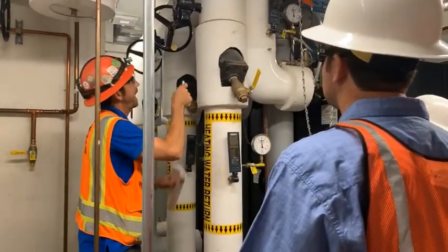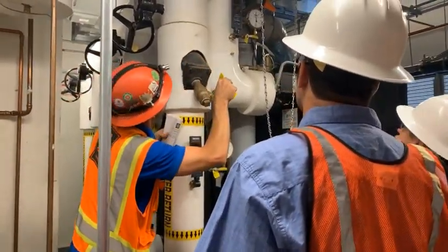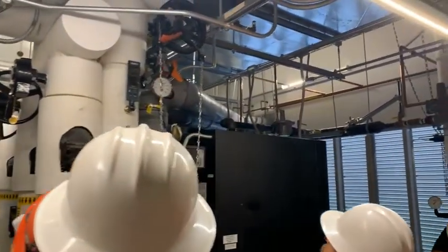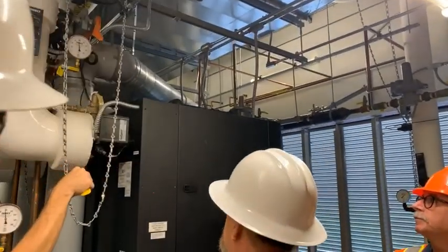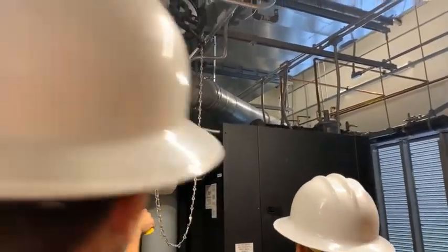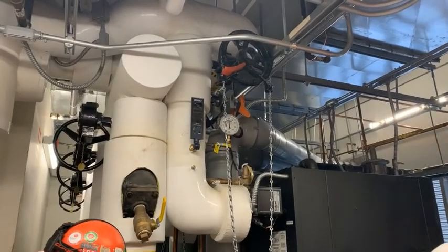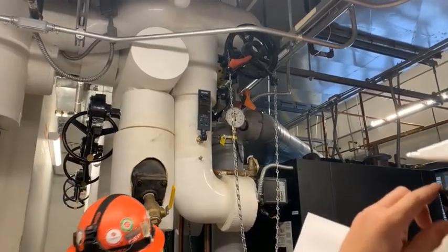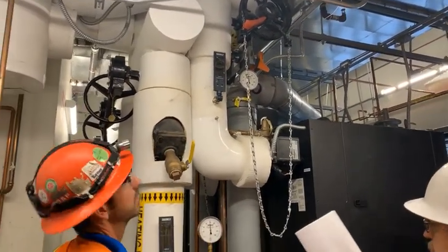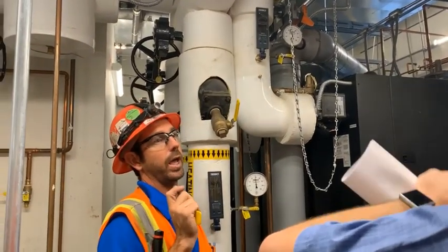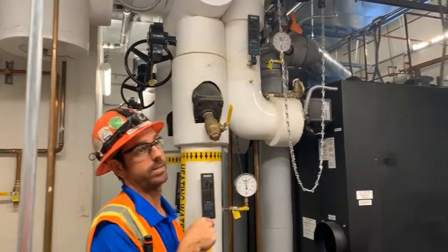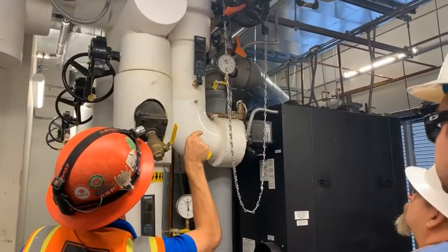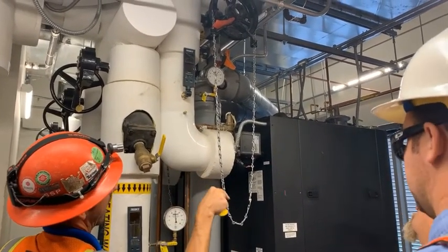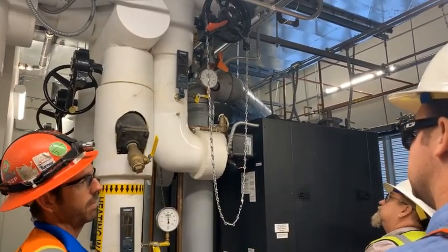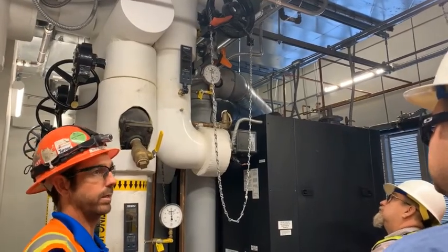Each boiler also has its own factory-provided control valve here. So this valve is operated from each boiler individually, okay? Valves, we have gauges, thermometers. And what is that, just for flow? It's firing. We'll have more training on that tomorrow. I just want to make sure that you know right now that that valve is being controlled from the actual boiler, not through BMS or anything like that, okay? And then we'll get into that more tomorrow.